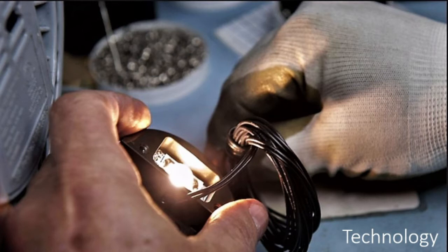So it's hard to believe that in 1988 you installed your first outdoor lighting system when you were 10. And tell us about the technology changes over the years. Back then in '88, when I was 10, incandescent bulbs, halogen bulbs, these bulbs would get so hot you'd burn your fingertips off and you couldn't touch the bulb, or your oils would screw up the halogen cycle of the lamp. We don't use aluminum fixtures. Aluminum fixtures in New England, due to the acidic soil and the salt content of the air around the coast, just weld up and they don't last and they deteriorate. So everything's brass and copper now.